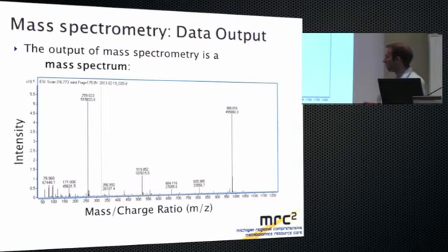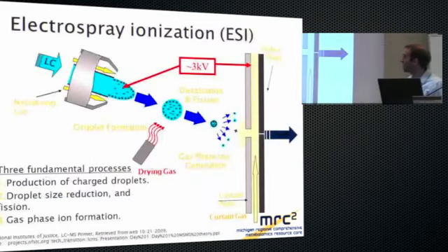So in a given mass spectrum, you may have multiple different peaks that come from multiple different metabolites, or may come from a reference signal. So here we have a peak for a metabolite, and we have an internal reference that is always present in all of our mass spectra that are acquired on a time-of-flight instrument. We'll talk about that, which we use to calibrate to make sure that the mass that we measure is as accurate as possible. And we may have other metabolites here. So we get two modes of resolution. We get both separation by chromatography and by mass spectrometry.